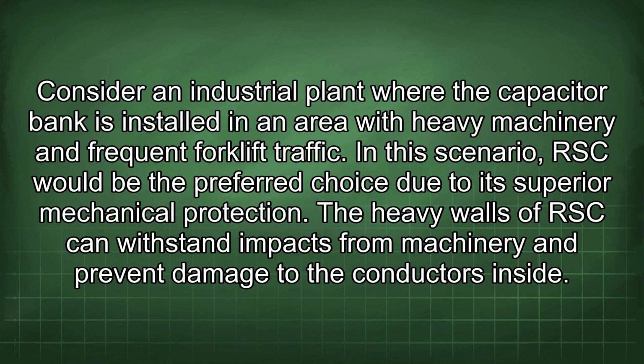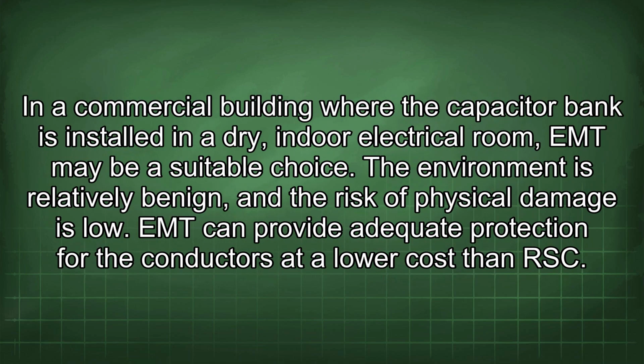Consider an industrial plant where the capacitor bank is installed in an area with heavy machinery and frequent forklift traffic. In this scenario, RSC would be the preferred choice due to its superior mechanical protection. The heavy walls of RSC can withstand impacts from machinery and prevent damage to the conductors inside. In a commercial building where the capacitor bank is installed in a dry, indoor electrical room, EMT may be a suitable choice. The environment is relatively benign and the risk of physical damage is low. EMT can provide adequate protection for the conductors at a lower cost than RSC.